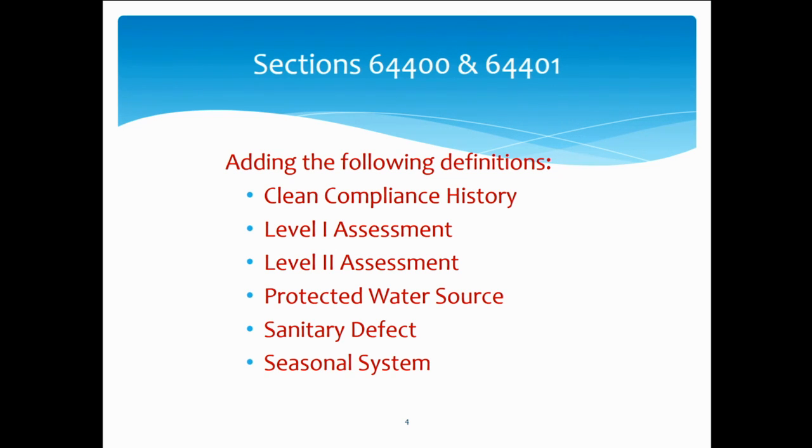Clean compliance history. That's essentially if you've had no monitoring violations, no MCL violations, no coliform treatment technique violations, and no treatment technique trigger exceedances, and we'll talk about what that means later in the presentation. The level 1 and level 2 assessments are defined. Protected water source is essentially an aquifer that has a physical barrier to preclude microbiological contaminants.